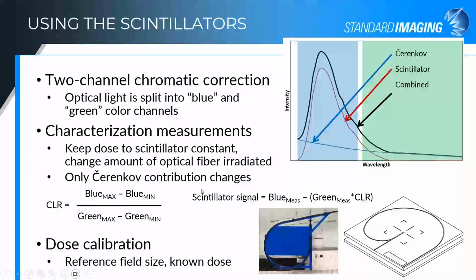From those 2 sets of measurements, we can calculate what we call a Cherenkov light ratio. This is the difference in the blue signal between the maximum fiber configuration, the large amount of fiber in the field, and the minimum fiber configuration, where you have a small amount of fiber in the field, divided by that same difference for the green channel. And from this, we get a correction factor that can be used. Multiply the CLR times the green channel measurement, and you subtract that from the blue channel measurement with your subsequent measurements, which gives you back just the scintillation signal.